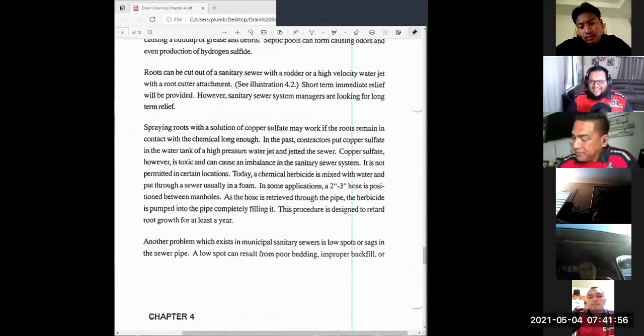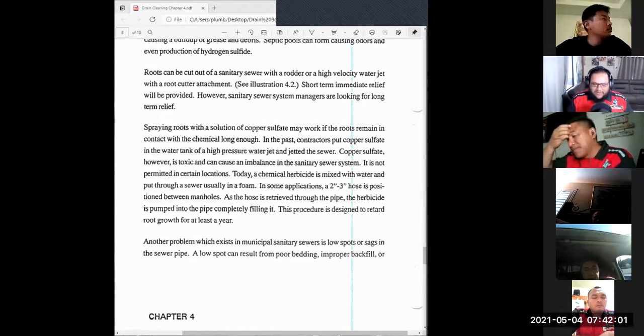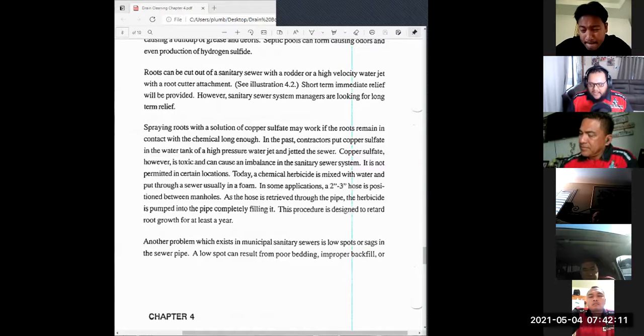I know it was tough, but when you've got the owner of the company telling you, while I'm running with my head cut off around this job site, Steve pulled me on the side, and I'll never forget it. This line collapsed, and it was my first liner job. The whole line collapsed in the drain. What happened was the customer flushed while we were in the curing process. And when we went to pull everything out, of course, the liner was completely closed.